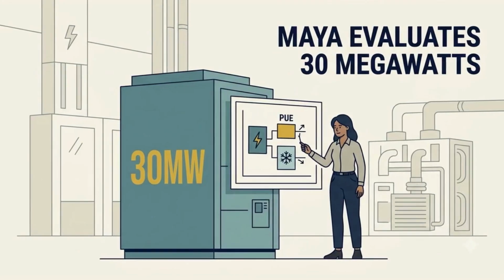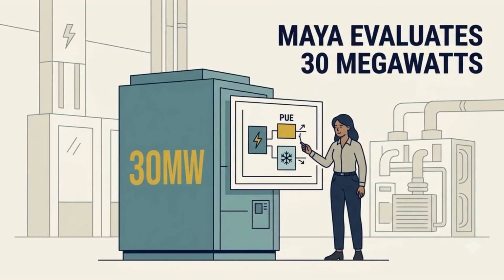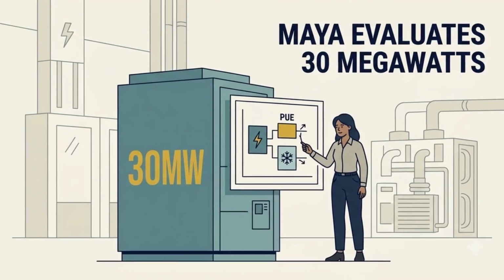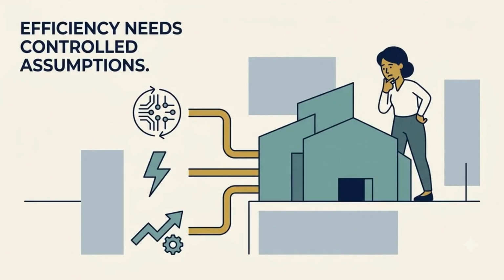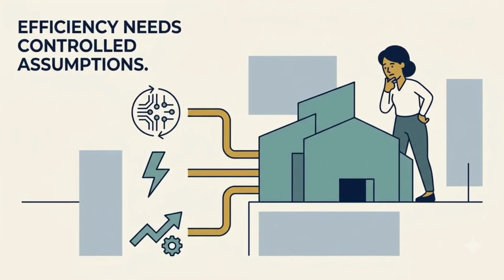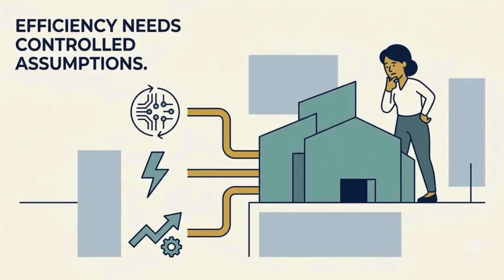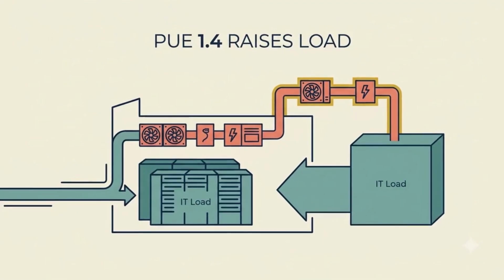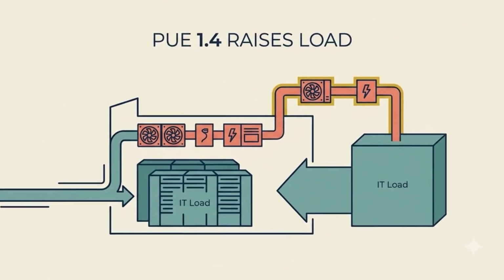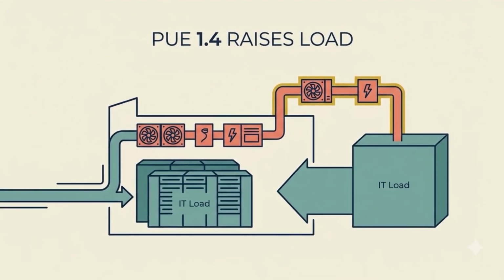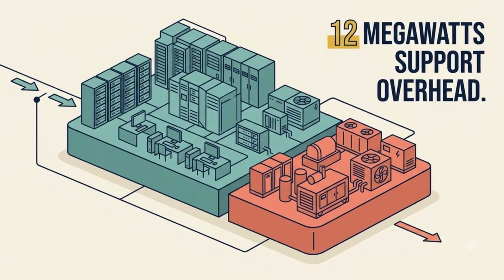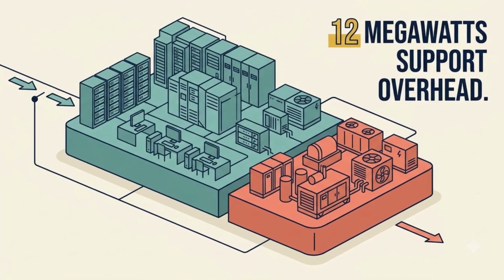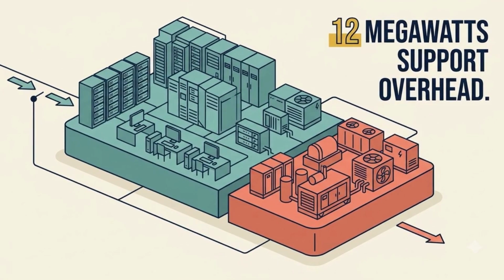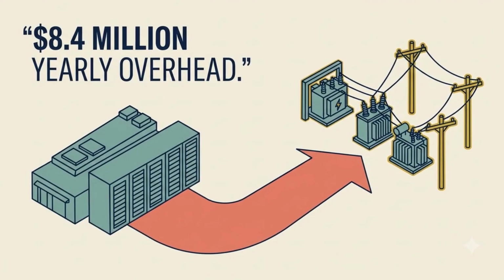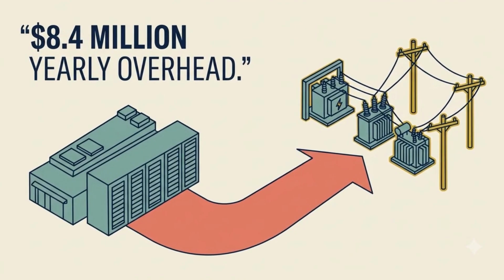Here is a simplified ownership example. Maya is evaluating a 30-megawatt IT facility. To isolate the effect of efficiency, assume the IT equipment runs continuously and electricity costs 8 cents per kilowatt-hour. At a PUE of 1.4, the total facility load would be 42 megawatts, meaning 12 megawatts are supporting the IT load rather than powering it directly. That overhead would cost roughly $8.4 million a year under those assumptions.